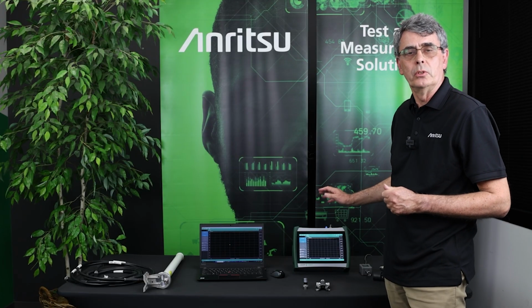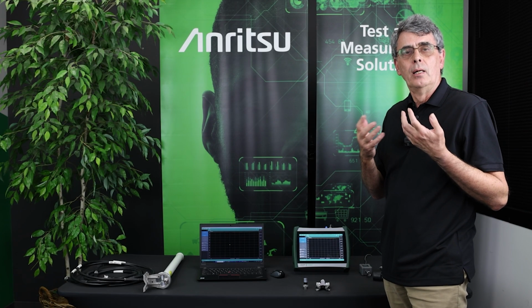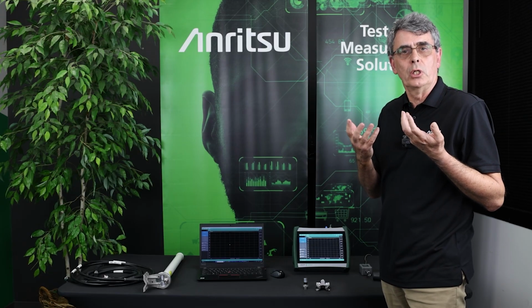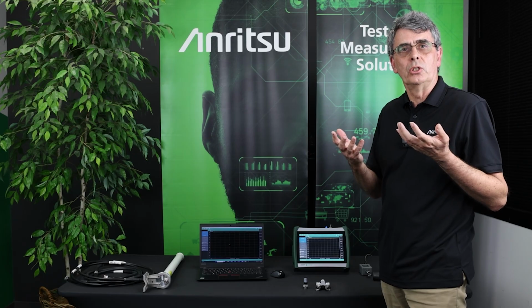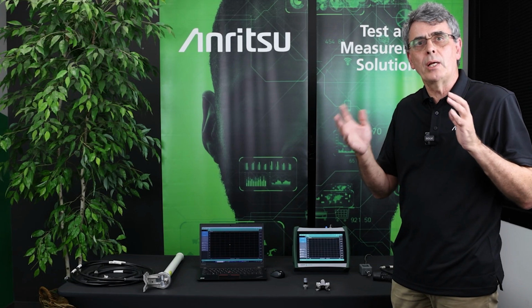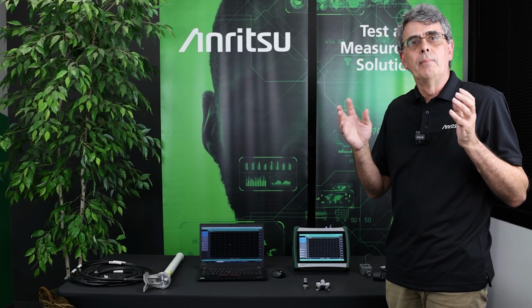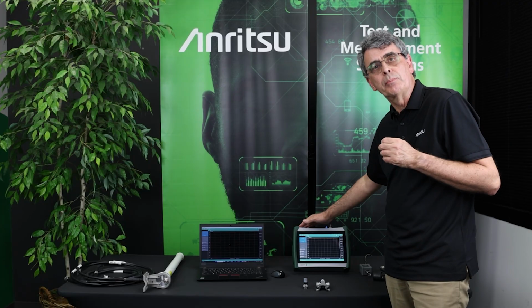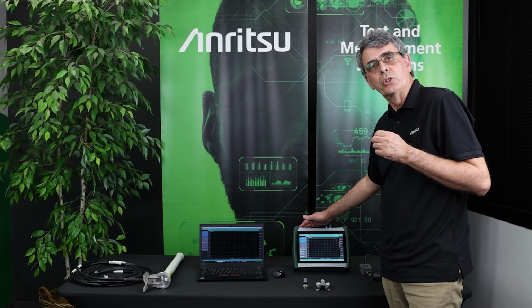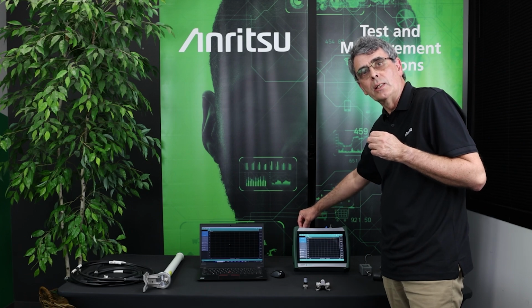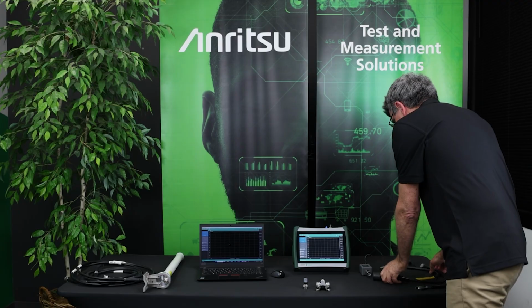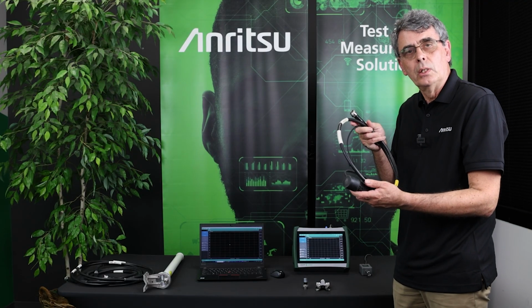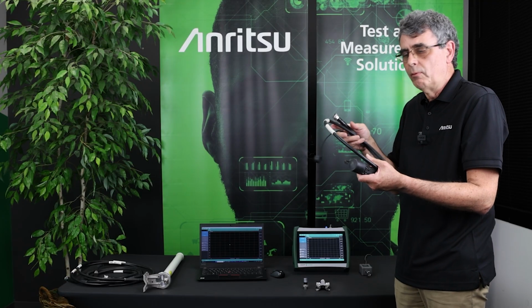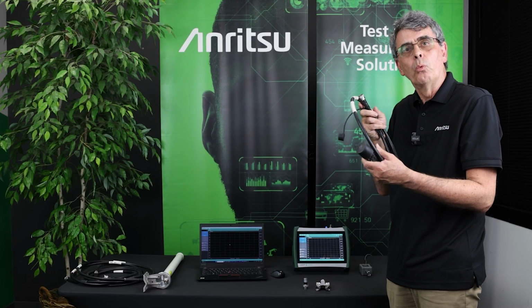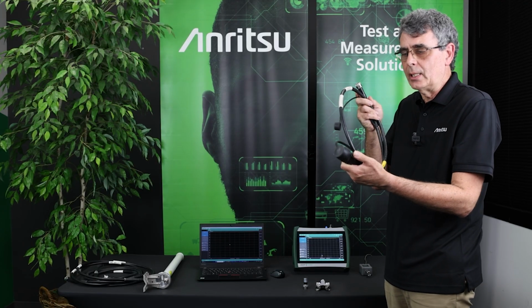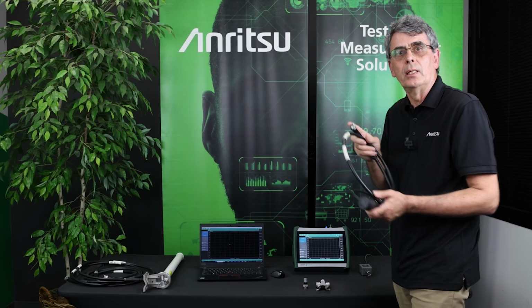When we manufacture the instrument, in production we generate calibration data that is good for making a return loss measurement or an insertion loss measurement under certain specifically defined conditions. Essentially those are if we're at ambient room temperature, around about 20 degrees centigrade, and if we're making a measurement at the test port itself, because that calibration data was calculated using calibration pieces on the test port. If we're using the test port cable to give us a 1 meter or 3 foot extension between the test port and the system that we're testing, we shouldn't be using the ReadyCal data because that isn't correcting for the errors introduced by the cable itself.